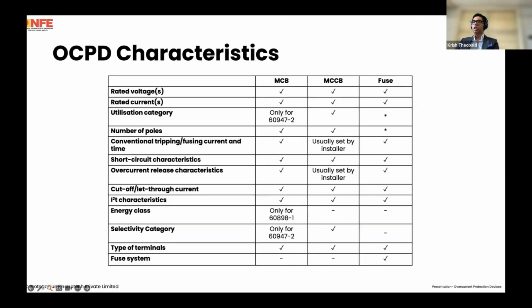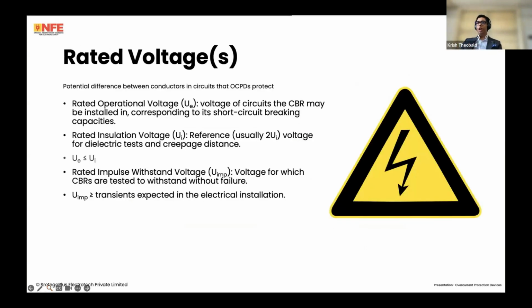Right. Now, when we come to rated voltages, basically this is talking about the potential difference between the conductors in the circuits that the OCPDs protect. We've got a rated operational voltage, which is denoted by UE. Basically, this is the voltage that corresponds to the circuit that the circuit breaker may be installed in. And for a given voltage, there is a given short circuit breaking capacity.